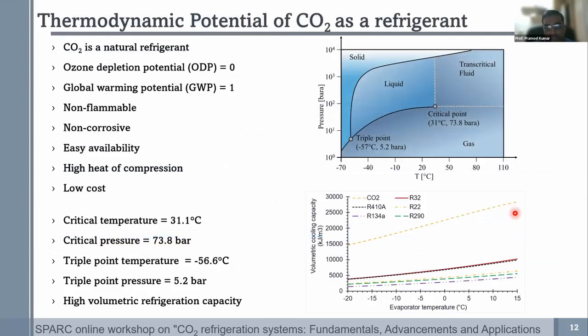Of course, I'm not going to get into this. What it tells you is that with carbon dioxide above 1 atmosphere, that means above atmospheric pressure, you can still achieve close to about -50 to -55 degrees Celsius, because the triple point is close to minus 57 degrees Celsius, and that is still substantially higher than the atmospheric pressure of 1 bar. The flip side is that since the critical temperature is low, where most of the ambient environments around the world are, you need to operate the system in a transcritical mode. We'll get back to this topic a little later.